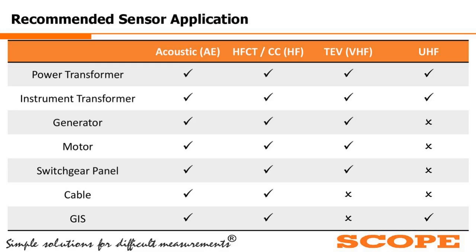Now, this is a very generic idea. This is no hard and fast rule on what kind of sensors you are going to use. This is a recommendation, as there is no IEC or any international standard that says you have to use this kind of sensor only. The recommendations given over here are given by IEEE or CIGRE, with the experience of the body that formed these recommendation panels. Based on their experience, they came to the conclusion that for this particular equipment, this particular frequency is most suitable.